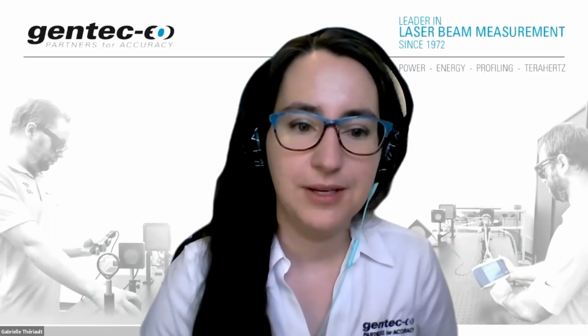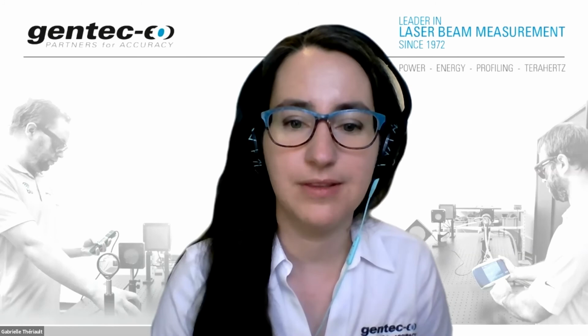Okay, next question. If we use a laser to set the equilibrium, is there any concern when zeroing the meter that we will not be able to account for a portion of the power? For example, if we're running 200 watts for 1 to 2 minutes, turn off the laser, and zero the meter with the display at 50 watts, since the meter is restabilizing without the laser, wouldn't we only read 150 watts, which would be inaccurate in that case?